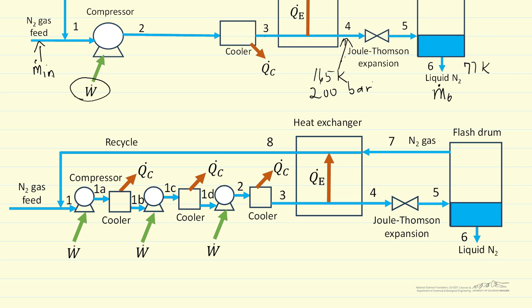So here I've shown three compressors where, for example, we go from one bar to five bar in the first compressor, and we remove heat back to room temperature. Go from five bar to 25 bar in the second compressor, and remove heat. In this case, we'll go from 25 bar to 200 bar in the third compressor.